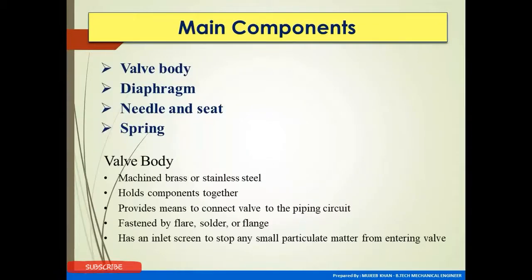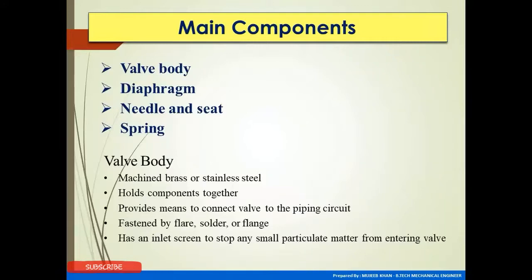The main components are the valve body, the diaphragm, needle and seat, and springs. The valve body is made of brass or stainless steel, holds components together, and provides a means to connect the valve to the piping circuit. It is fastened by flare, solder, or flange, and has an inlet screen to stop any small particulate matter from entering the valve.